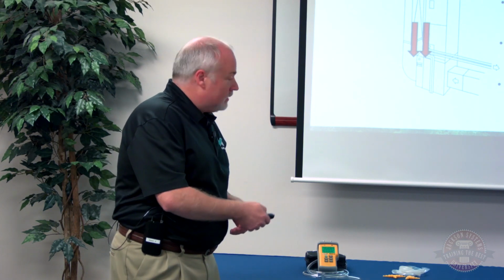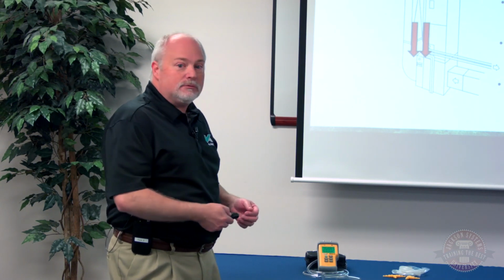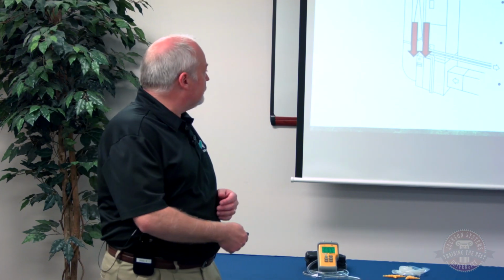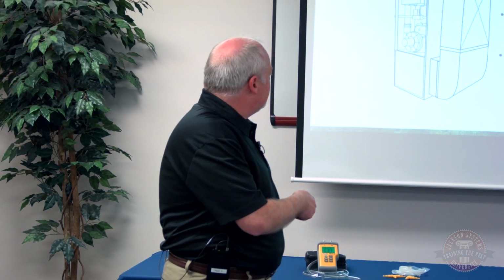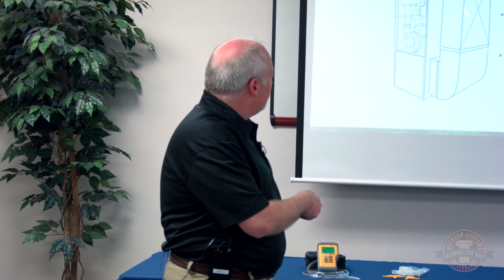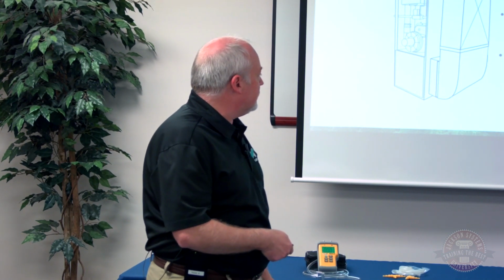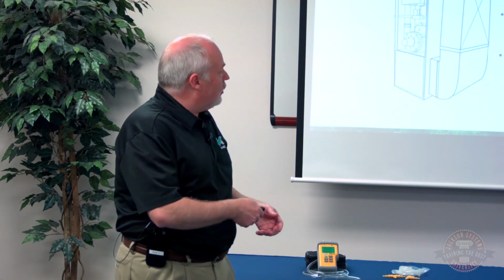Okay. Let's say our air filter was proper, we had the proper air drop. Well, let's look at our coil then. In this case, we're going to look at our inlet to our coil and our outlet of our coil, and we're going to take the difference between those two readings. The manufacturer specifications are going to tell you what the drop should be across that coil. If I've got a higher drop across that coil than I would expect to find based on the manufacturer sheet, I've probably got a dirty coil in there. I need to clean that so I can get a proper airflow across it.